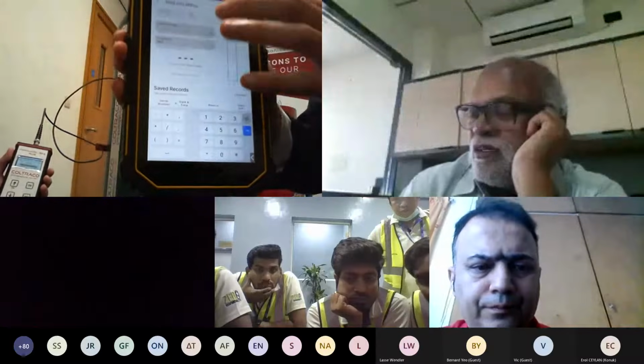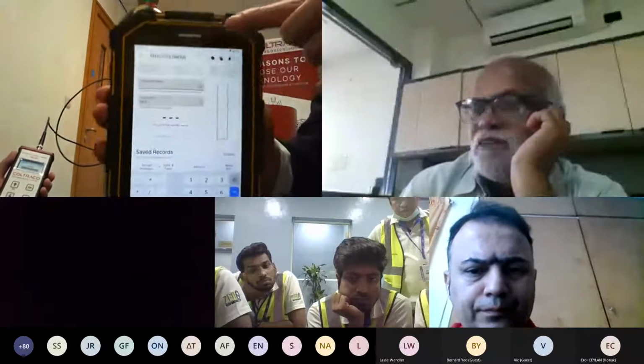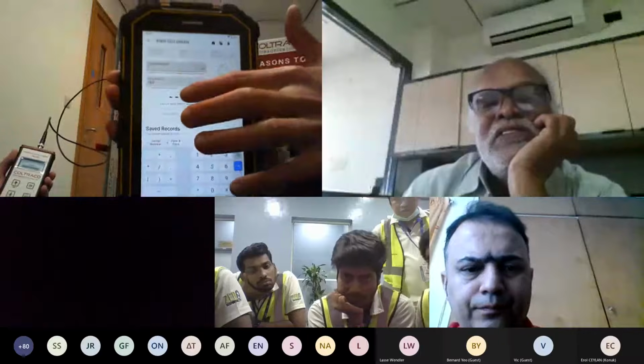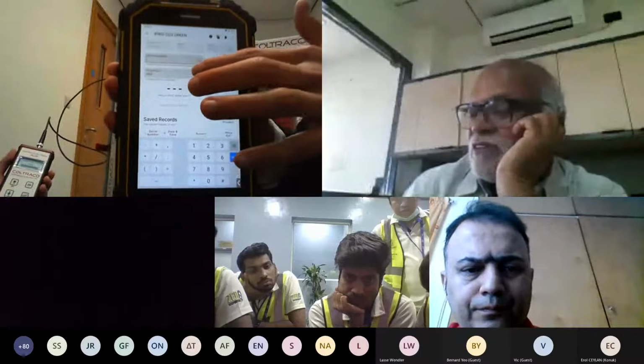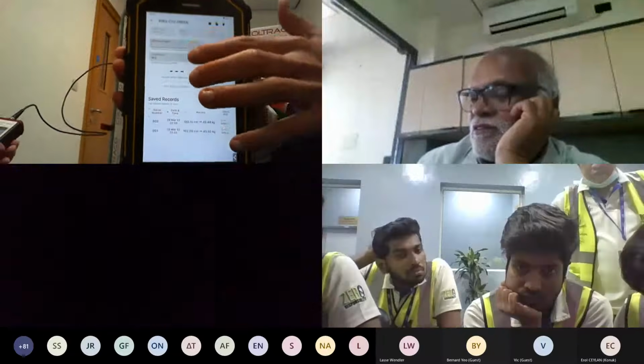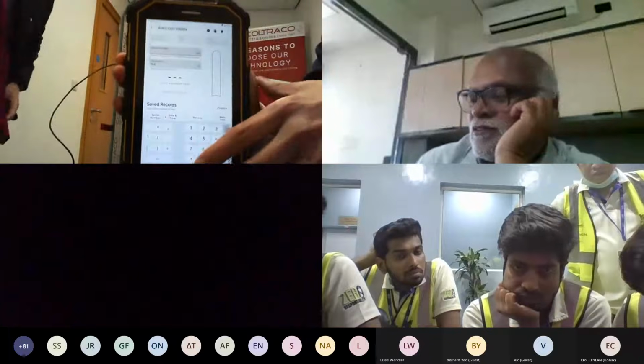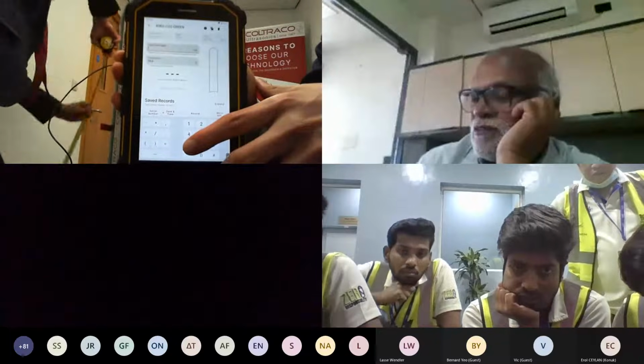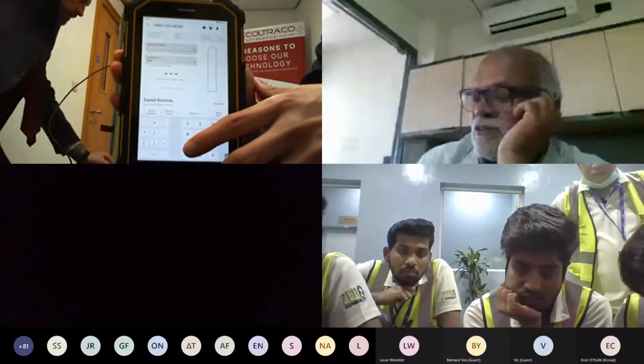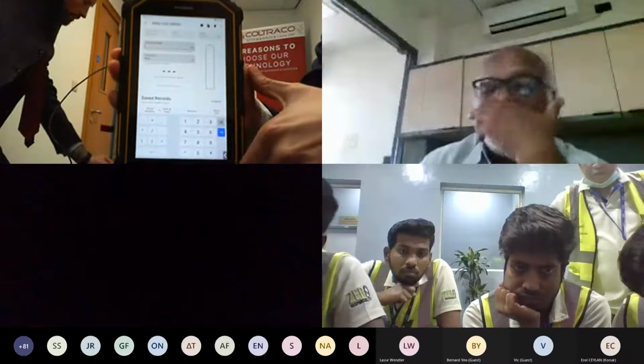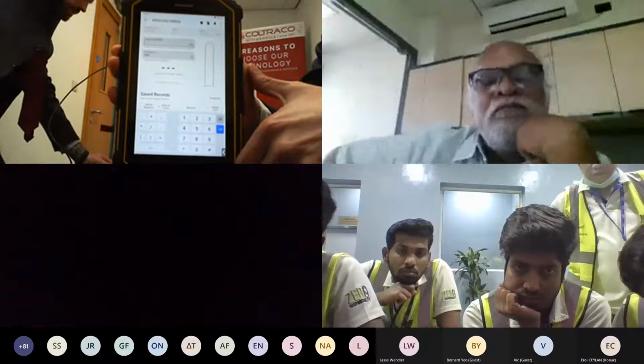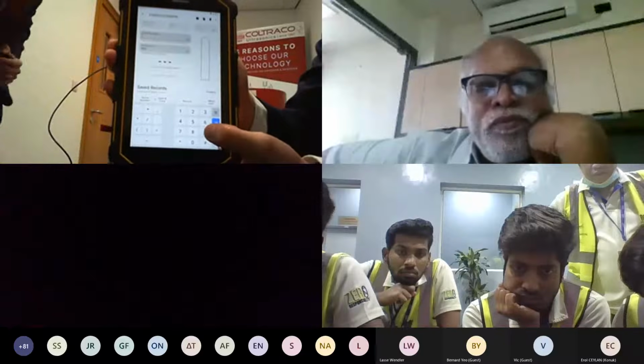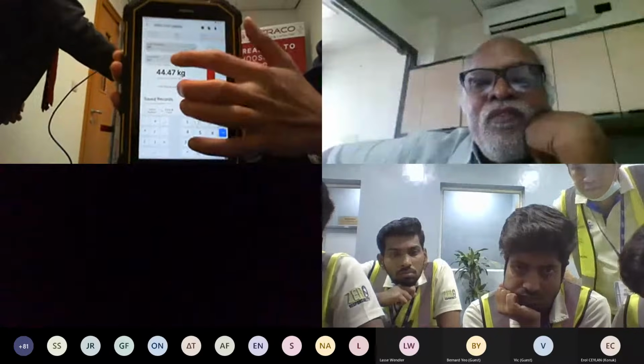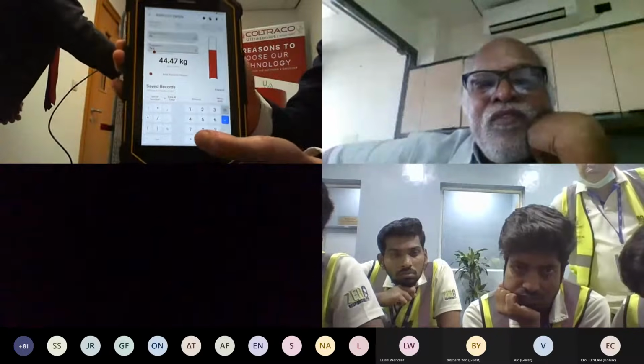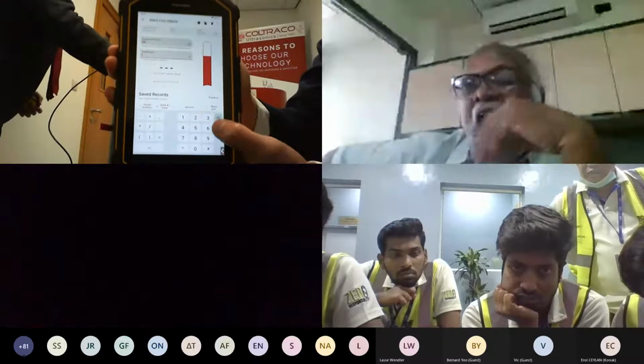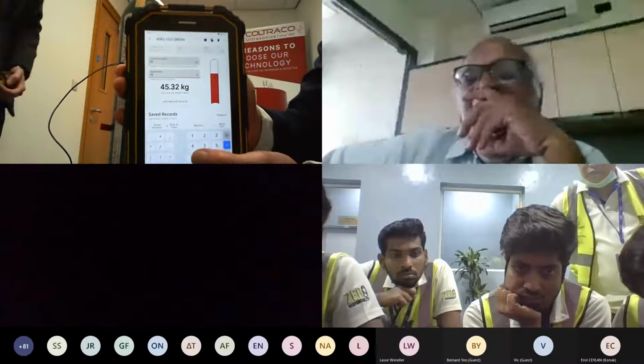Now, when Benjamin has measured the liquid level height found using the Portalevel Max Plus and the temperature, this device will provide a corresponding agent mass. So Benjamin, what is the liquid level height? It was 99 centimeters. I always double check, Adrian. 99 centimeters. So the liquid level is 99, and the temperature? 11 degrees. The temperature is 11 degrees.